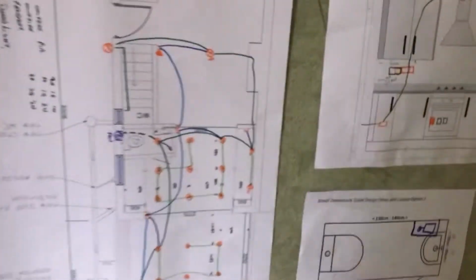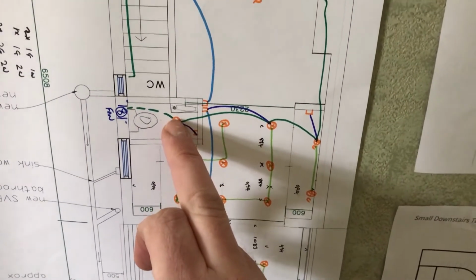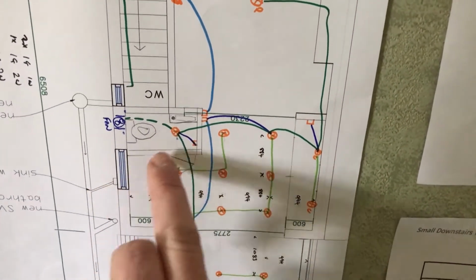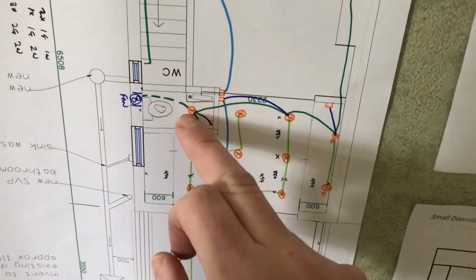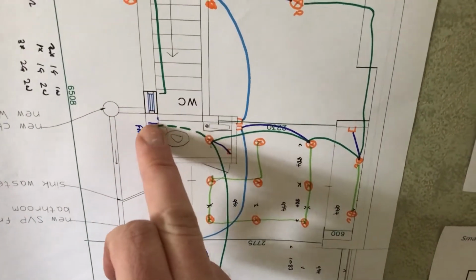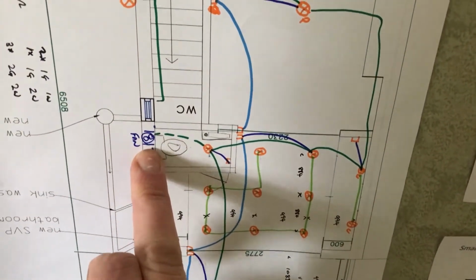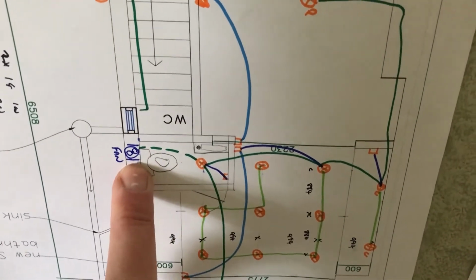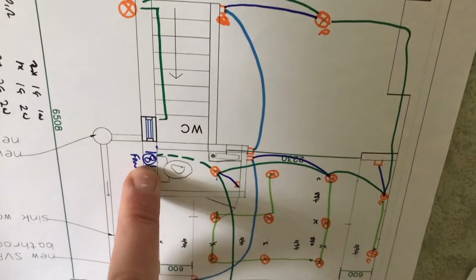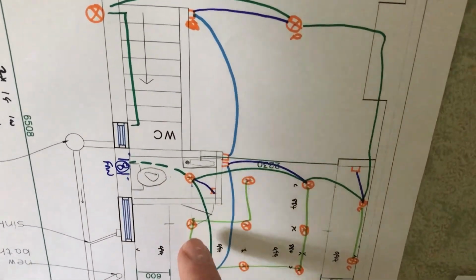Now this is why it's good to plan your lights out on a piece of paper, because my toilet's not even there yet. So the power comes into the toilet light. It just needs a single way switching on this one. So the fan needs power, so you will need to take a supply off the permanent light and the switch live to operate your fan. And generally speaking, it's best to put that on an isolator. So we'll probably have an isolator just by the door there.